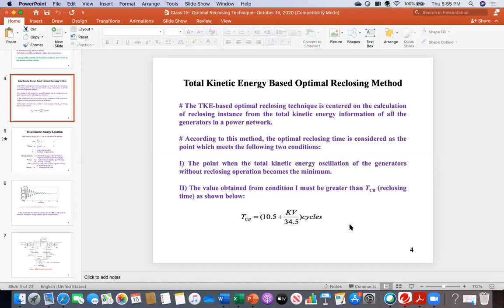So 20 milliseconds multiplied by the cycles you got. We got 11.07 cycles, multiplied by 20 milliseconds, so I am getting 221 milliseconds. If you divide by 1000, that is 0.22 seconds. So by calculating this, the TCB timing I got is 0.22 seconds. It says the value obtained from condition 1 must be greater than TCB. This means you must wait until 0.22 seconds to reclose the breaker. You are not allowed to reclose the breaker before that time. That is the meaning of this.